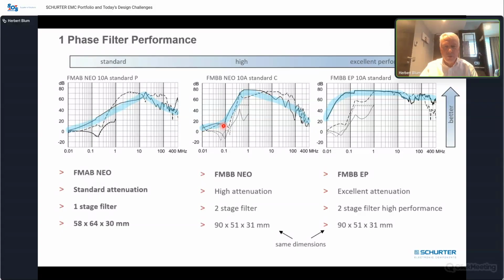Then we can use a dual stage filter, and then we get about 80 dB of attenuation here in the middle frequency range. That's good, and we also get better performance here in the lower frequency range. Conducted measurement starts here at 150 kilohertz, and it goes up to 30 megahertz. So it's this range here in the middle, and here it performs quite well. Now, this is one stage, two stage, as I said, 80 dB. With these two together, I cover 80% of all applications for sure.